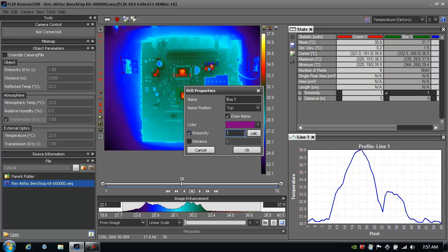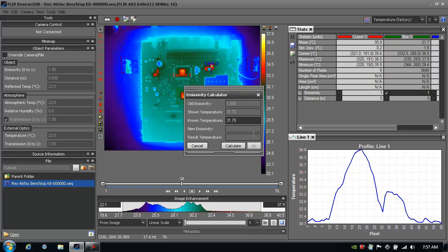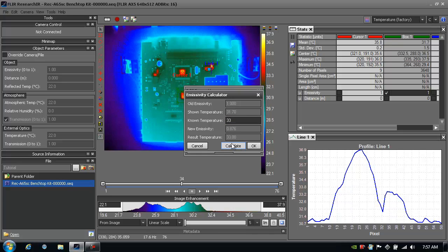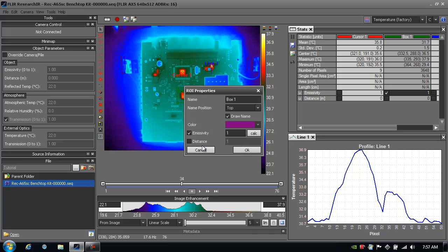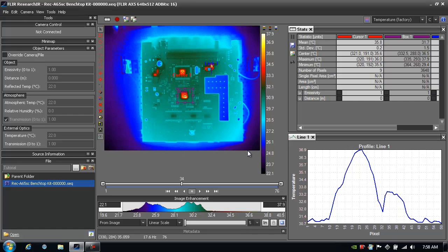Now, if, perchance, I don't happen to know the emissivity, I can calculate it here in Research IR. So I just heat my board to a known temperature, and then I can type that in here. So let's say, for example, the infrared camera is measuring 31.7C, but the reality is it's really 33C. I would calculate, and the emissivity should be 0.876. And I could then use that new emissivity. Today I'm going to leave everything kind of as the default, so I'll uncheck that. But I do want to change the color so I can see it a little better.